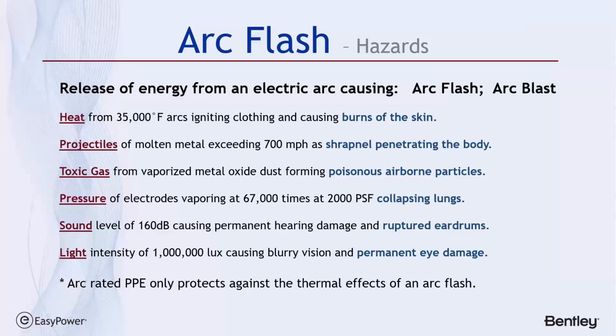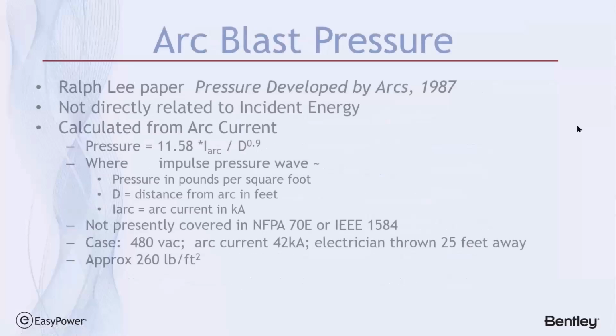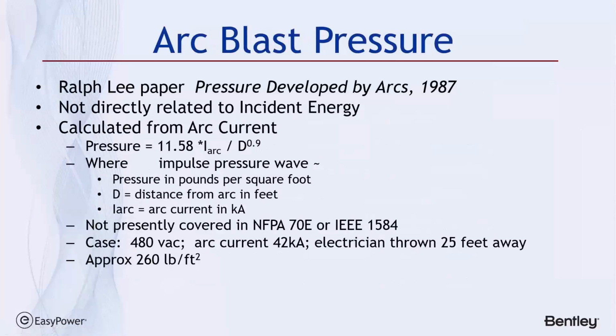I'd like to include one slide on the term arc blast. The second hazard that Ralph Lee described was a pressure developed by arcs. Because not enough time has been spent to characterize the blast pressure itself, it still, I guess, doesn't receive its due, or it's not something we can quantify. So again, it's not presently covered by NFPA or IEEE 1584. There is a one paragraph note on it, and it basically contains the information I have here on the slide.